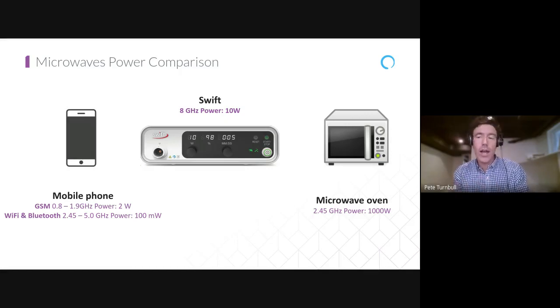The system can go higher, but it's your tip, the actual disposable tip, that regulates the amount of power coming out of the device. It's got sensors built into it to say, this is a podiatry-based tip, we only want to allow 10 watts maximum. So 8 watts of power compared to a microwave oven is very different. It is more akin to taking a phone call with your phone up against your foot. Any smartphone uses microwaves to transmit, and they operate at 2 watts of power. Swift is at 8, so it is much more like a cell phone than a microwave oven, if that makes sense.